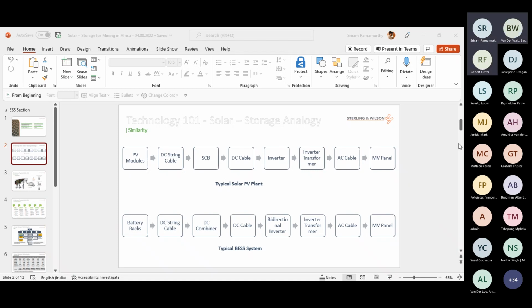And the DC to DC? Is that fairly constant across suppliers, or is it very supplier specific? It would vary a little bit, but fundamentally the depth of discharge is the main factor that hits it. Other than that, all the other factors remain the same for most suppliers, because the DC combiner boxes, DC cables, PCS, and transformers all have losses that remain the same going forward. The DC to DC efficiency is close to 92 to 93% approximately, though these are rough estimates depending on what we've done.